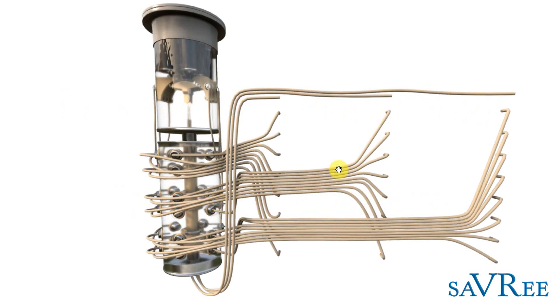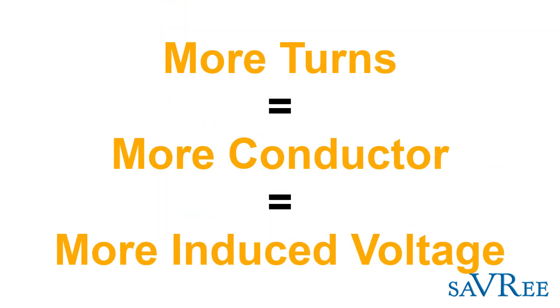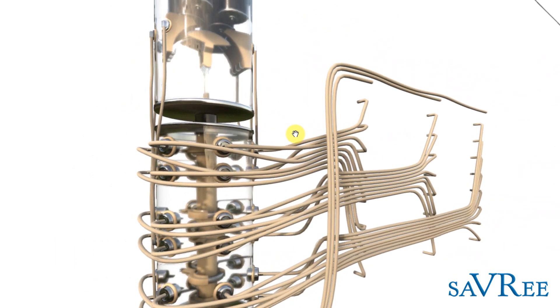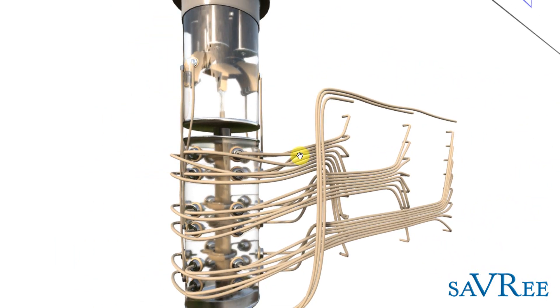So in other words, if we've got a secondary winding with 10 turns, less voltage will be induced than if we had a secondary winding with 20 turns. So the number of turns within the change in magnetic field dictates the amount of conductor within the change in magnetic field, and this ultimately dictates the amount of voltage that is induced within the conductor. So we will use the tap changer for changing the number of turns on the secondary winding and thus changing the output voltage.